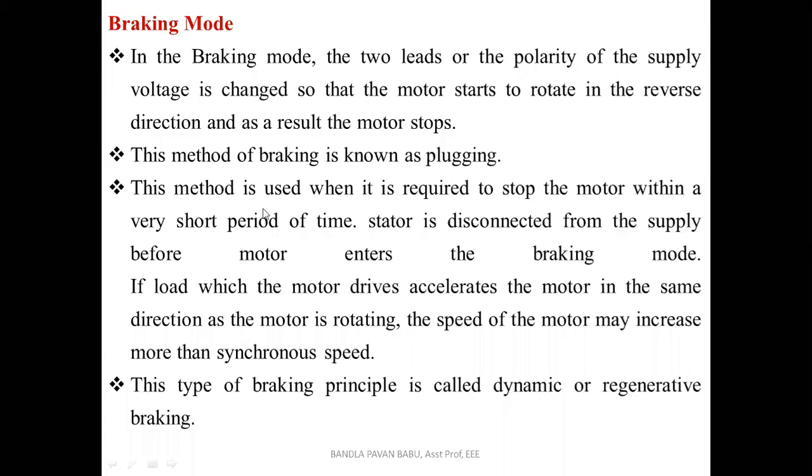So this method is used when it is required to stop the motor within a very short period of time. The stator is disconnected from the supply before the motor enters the braking mode. Suppose you want to apply the braking mode, we need to remove the supply, and any two of the terminals may be reversed. So immediately the motor decelerates, and it stops rotating.